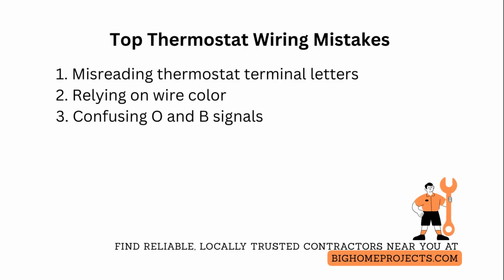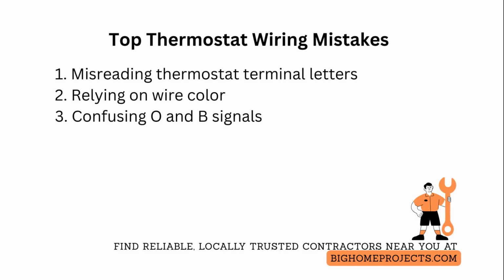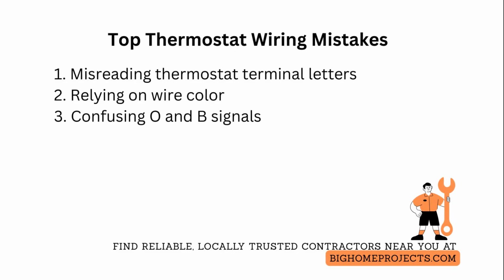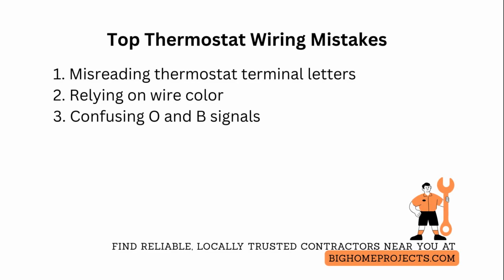One of the third pitfalls is confusing O and B reversing valve signals in heat pump systems, causing reverse operation. Correct that by consulting the air handler or outdoor unit wiring diagram and setting the thermostat to the specified reversing valve polarity.